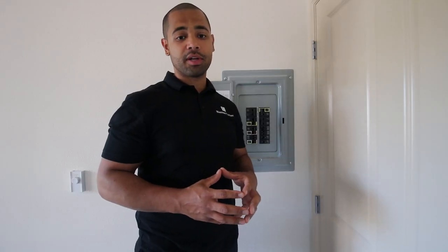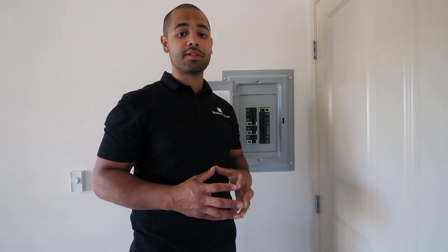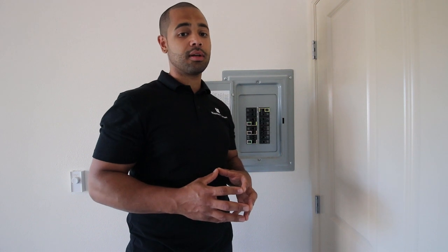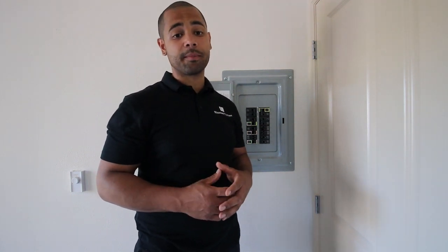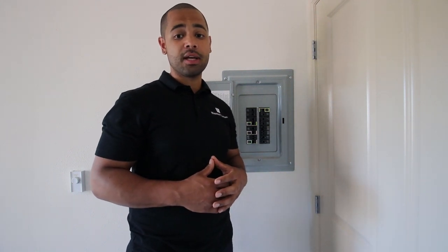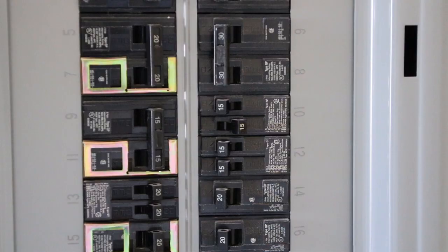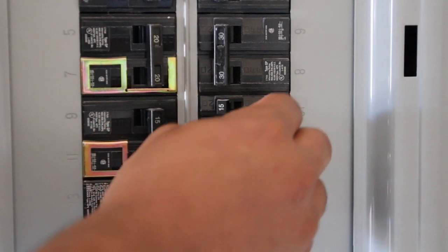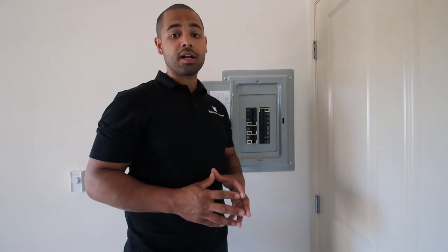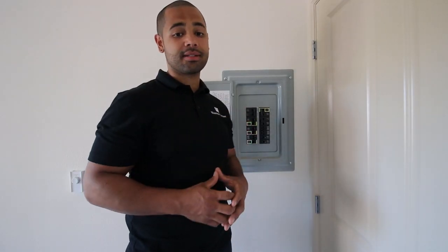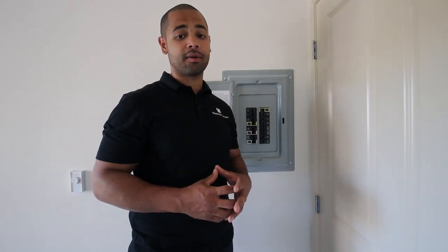Sometimes, when a breaker trips, the control switch doesn't always fully retract to the off position. It may appear that the circuit is on, but we know that the electricity is not running. No matter the case, in order to attempt to restore electricity to the given circuit, move the switch firmly to the off position and then back fully to the on position. Then watch the breaker for at least 5 seconds to make sure that the issue has been fully corrected.